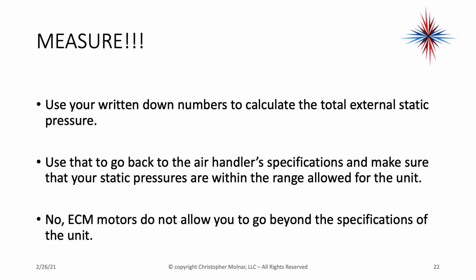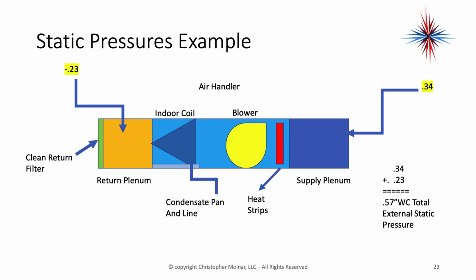ECM motors do not allow you to go beyond the specifications of the unit. That's a common misconception out there. ECM motors still have a range and still have specifications for you to be at. So here's an example. I have a negative 0.23 in my return and a 0.34 in my supply. You take these two numbers, drop the signs, and add them together. So I come up with 0.57 inch water column total external static pressure.